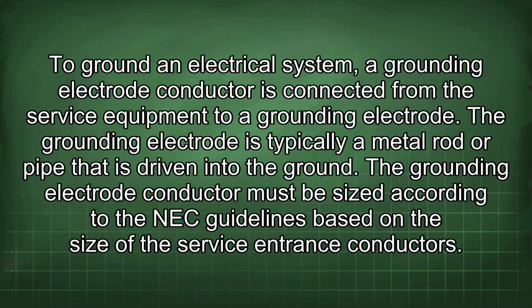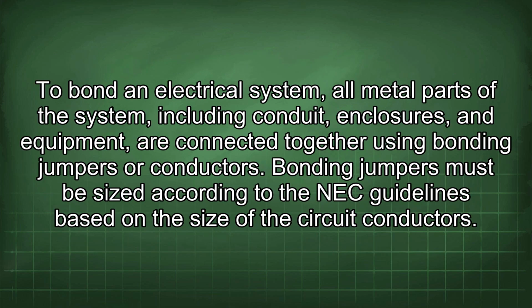To ground an electrical system, a grounding electrode conductor is connected from the service equipment to a grounding electrode. The grounding electrode is typically a metal rod or pipe that is driven into the ground. The grounding electrode conductor must be sized according to the NEC guidelines based on the size of the service entrance conductors. To bond an electrical system, all metal parts of the system, including conduit, enclosures, and equipment, are connected together using bonding jumpers or conductors.